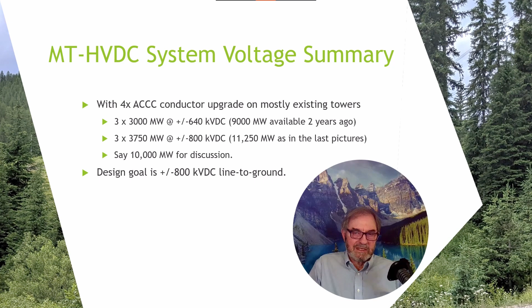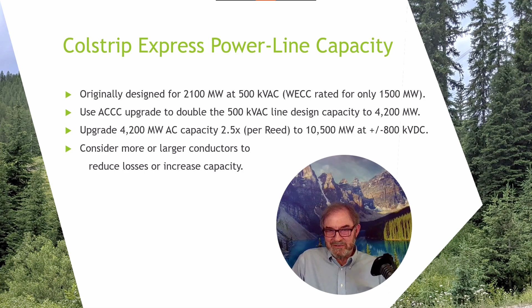The Colstrip Express power line capacity calculations. Originally designed for 2,100 megawatts at 500 kV AC, although only WECC rated for 1,500 megawatts. We can use the ACCC conductor upgrade to double the 500 kV AC line design capacity from 2,100 to 4,200. And then we can increase that capacity 2.5 times following the Reed paper to 10,500 megawatts at plus or minus 800 kV DC. We can also consider more or larger conductors to reduce losses or increase capacity.